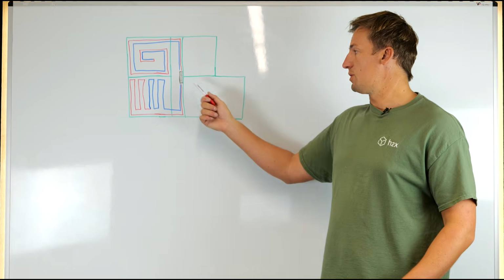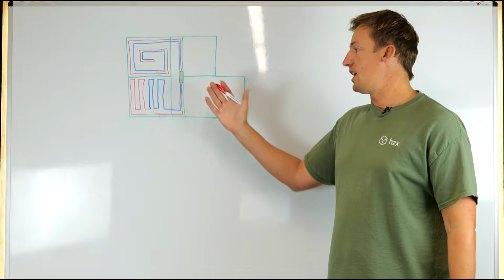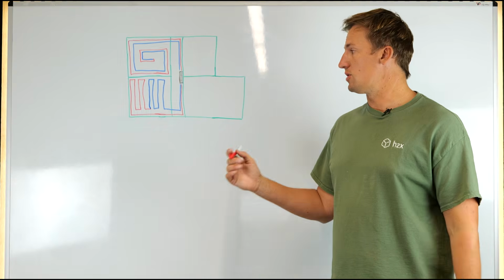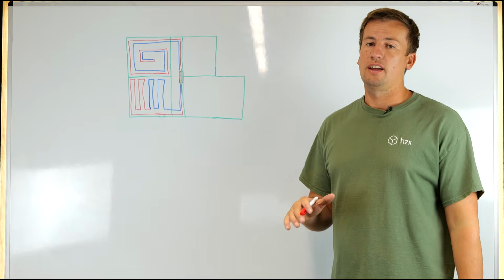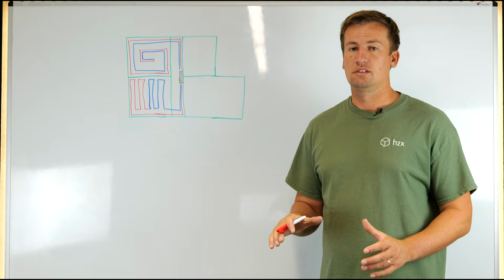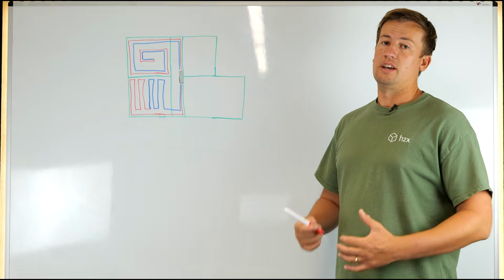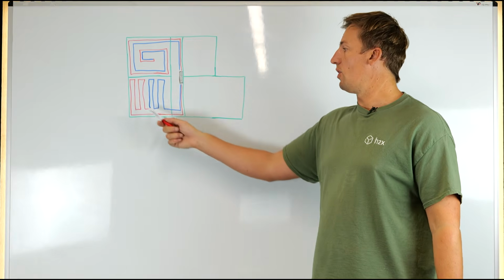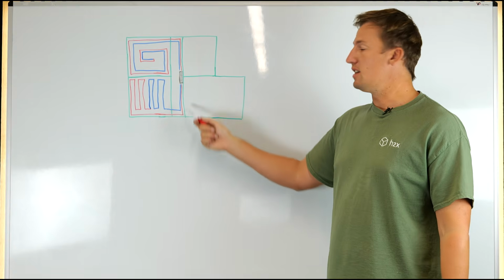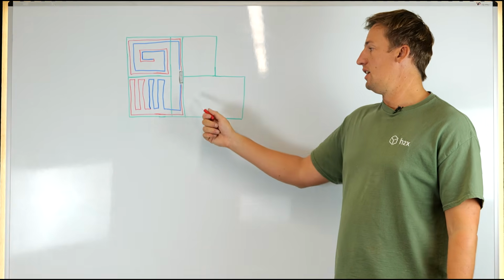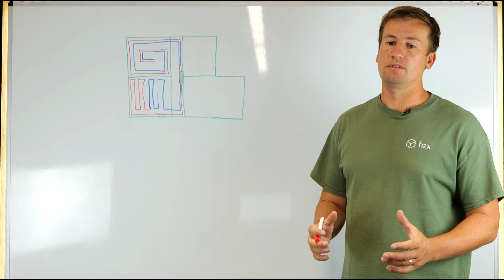And what's really important to understand about the transit pipes is they have hot water in them, and they are going to be wanting to emit heat as soon as they leave the manifold. And although some people like to design that way, it isn't the best practice. Reason being is we've done our calculations. The heat emitted and the heated area is only based on this room. So if we're allowing our system to emit heat in other rooms like the corridor, that means there's going to be less heat to emit when we get to the room, which is not good.